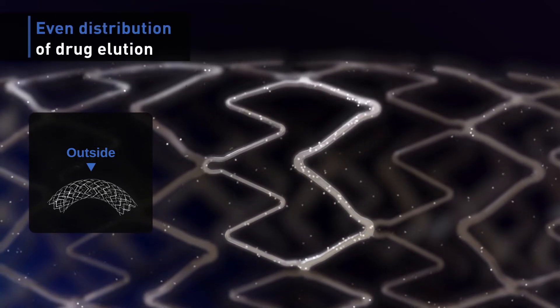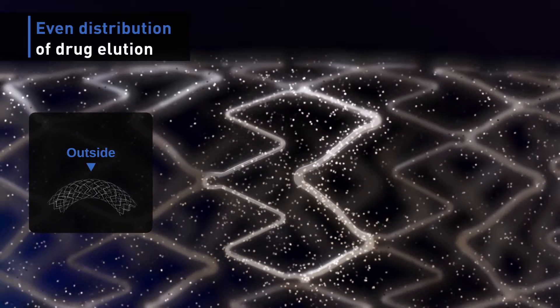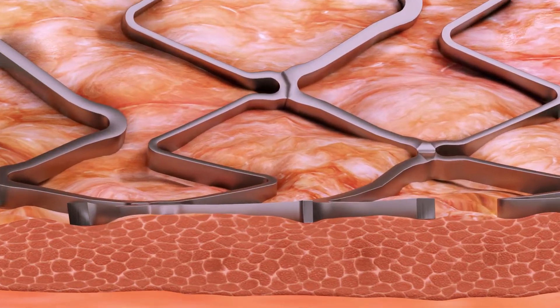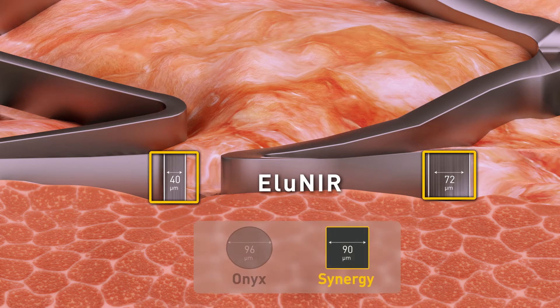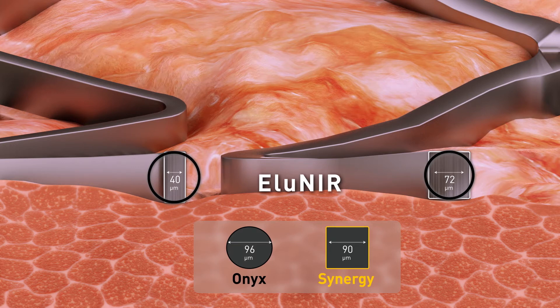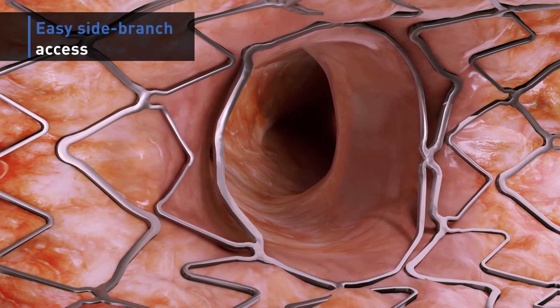Even when deployed on curved segments and during myocardial contractions, while other stent designs allow large openings, contributing to tissue prolapse and, potentially, restenosis. This design provides EluNIR with a very low metal footprint compared to other stents, lowering vessel trauma and improving healing. The ultra-narrow struts also allow for easy access to side branches.